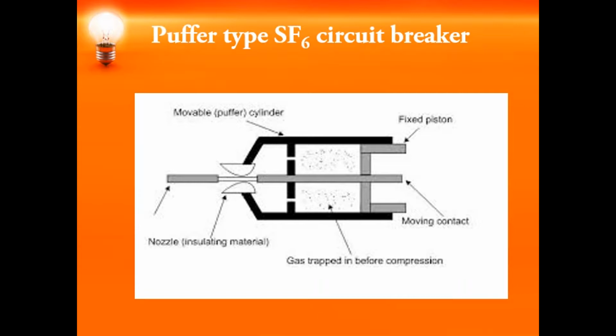In SF6 circuit breakers, SF6 gas is blown axially, that is along the arc, during the arcing period. The gas flowing along the arc removes heat from the arc by axial convection and radial dissipation. Due to this, all the ionized particles get removed. We'll see puffer type SF6 circuit breakers. You have puffer type and non-puffer type. Here we are going to see the puffer type. In this type of circuit breaker, the SF6 gas is compressed by the moving cylinder system. You can observe here a fixed piston, a moving contact, a nozzle, and SF6. This is the gas trapped before compression.